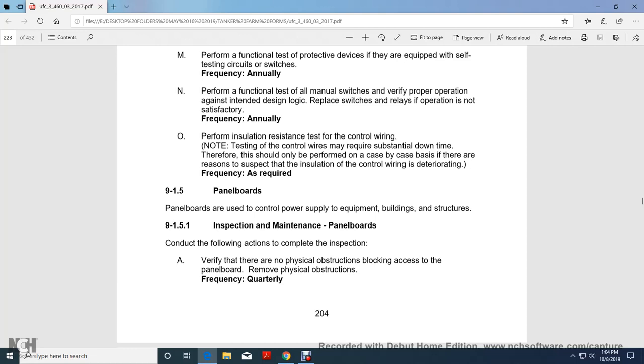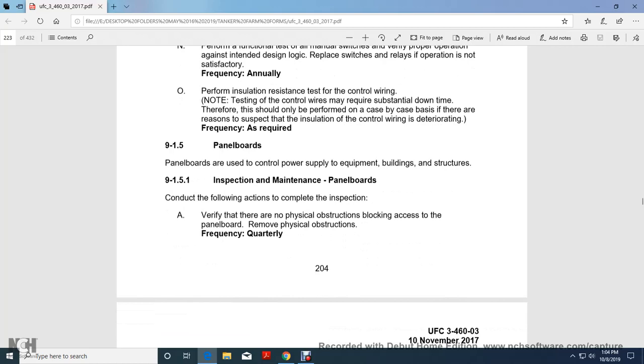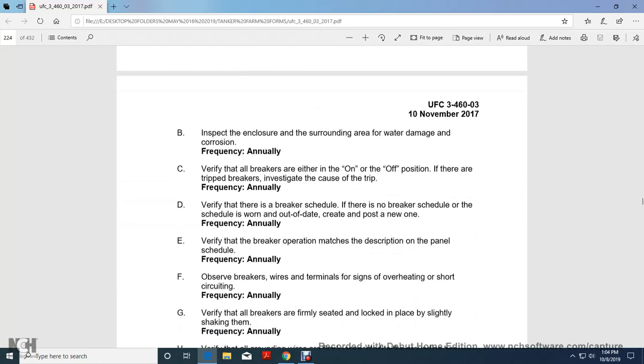Panel boards are used to control the power supplied to equipment and the building structure. For inspection of panel boards, complete the following actions. Verify that there is no physical obstruction blocking access to the panel board, and remove any physical obstruction, quarterly. Inspect the enclosure for surrounding air, water damage, and corrosion, annually. Verify the breakers are in the on or off position. If there are tripped breakers, investigate the cause of the trip, annually.